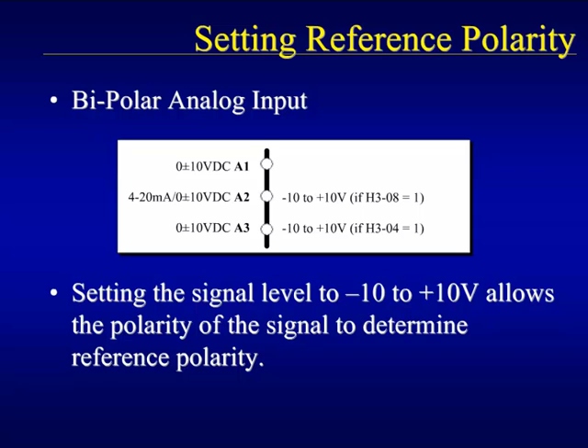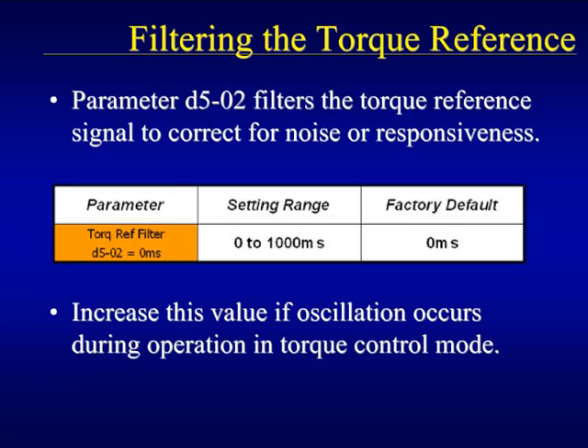Another method of changing torque reference polarity is by setting up the analog input being used for the torque reference as a negative 10 to plus 10 volts signal level. When the reference signal is between 0 and positive 10 volts, the torque reference will be in the same direction as the forward run command. Conversely, if the signal is between 0 and negative 10 volts, the torque reference will be in the opposite direction as the forward run command. Electrical noise or poor signal quality may cause an errant torque reference signal. Adding a filter to the torque reference will reduce the effect of fast signal variations. Parameter D502 can be configured to continuously filter the torque reference for time periods of up to one second. This does not mean that the torque reference will change only once per second, but that all of the values of the previous second will be averaged to filter out any spikes that may occur on the signal.